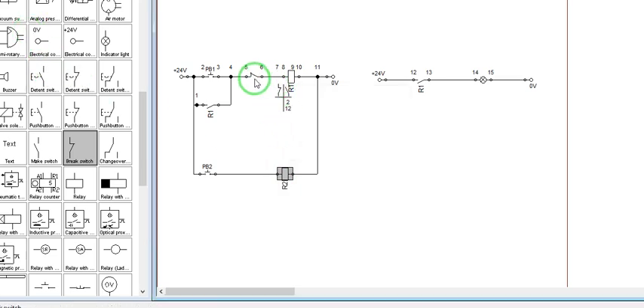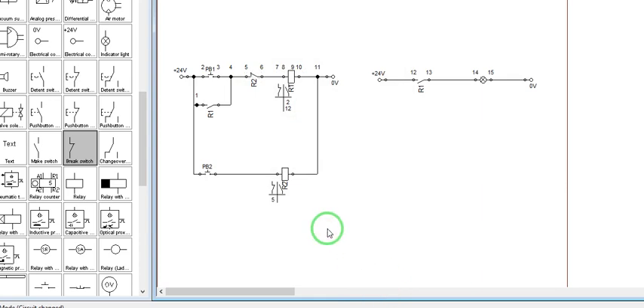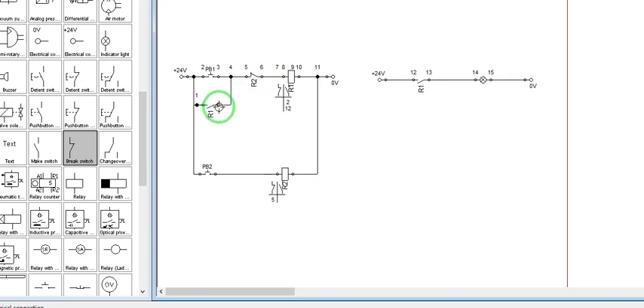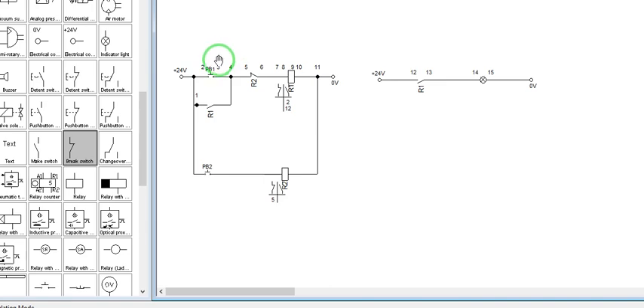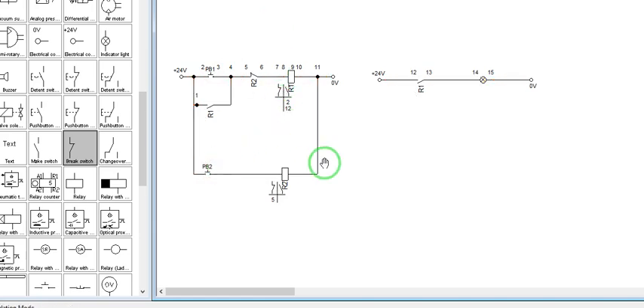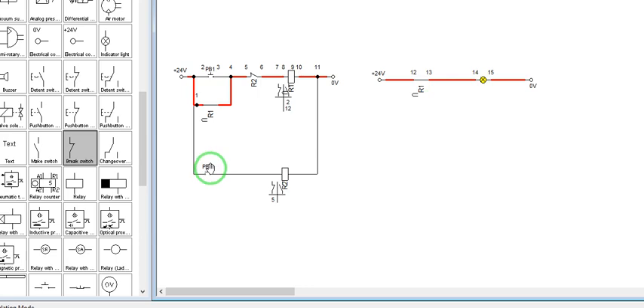If you recall our second experiment, the unlatching contact is connected in series with the auxiliary contact R1. But for reset priority, we put it here. If we run this simulation and press Push Button 1, press and release, the circuit will latch. If we press Push Button 2, the circuit will unlatch. Again: Press Button 1 — R1 is latched, energizing the load lamp. Press Push Button 2 — R1 is unlatched, thereby de-energizing our lamp.